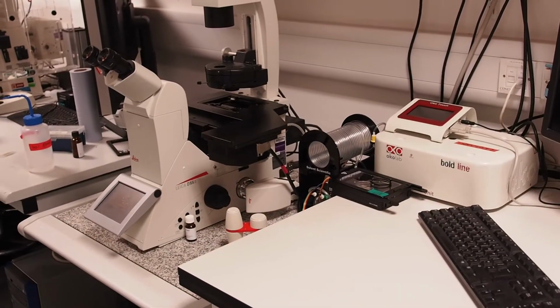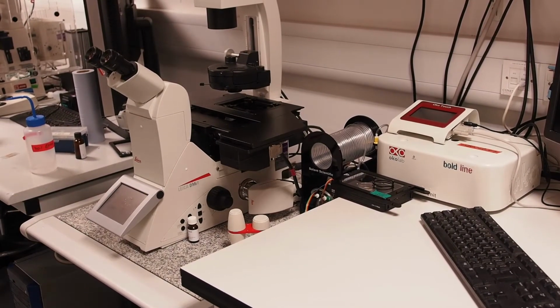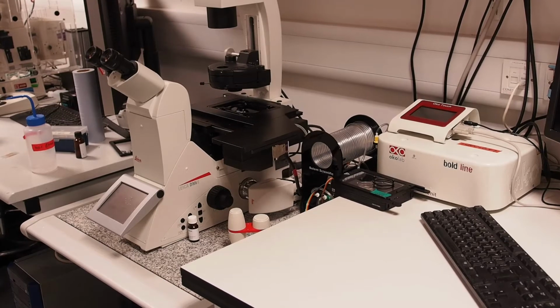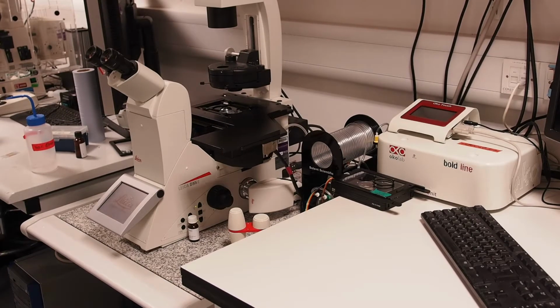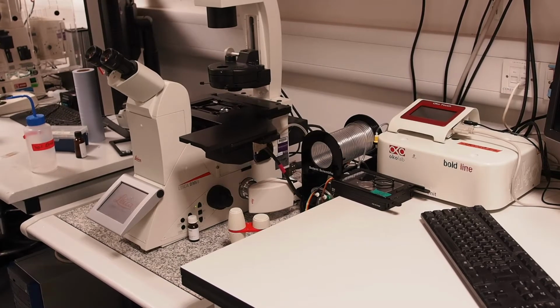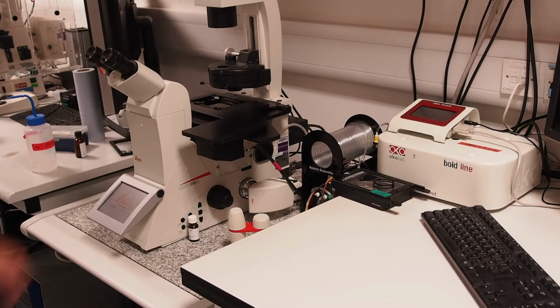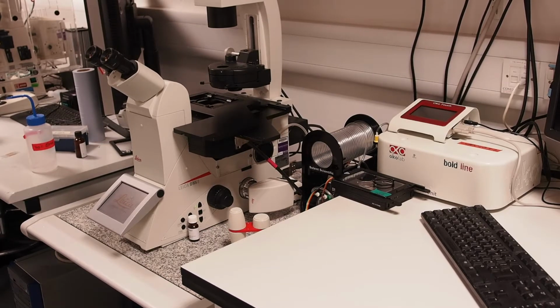Wait for the microscope to boot and finish carrying out a stage calibration routine, and then log into the PC. Once the LCD screen on the microscope has completed booting and the stage has finished its calibration, you can proceed to load your sample.